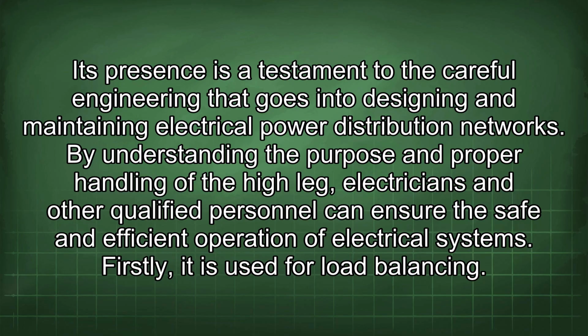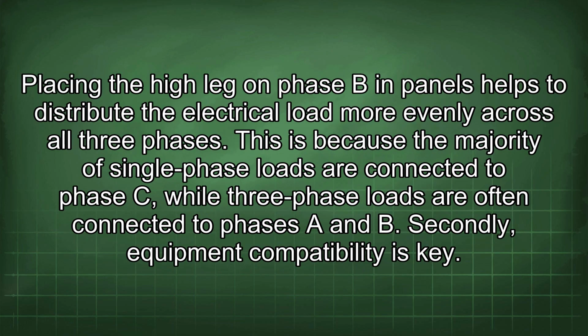Firstly, it is used for load balancing. Placing the high leg on phase B in panels helps to distribute the electrical load more evenly across all three phases. This is because the majority of single-phase loads are connected to phase C, while three-phase loads are often connected to phases A and B.